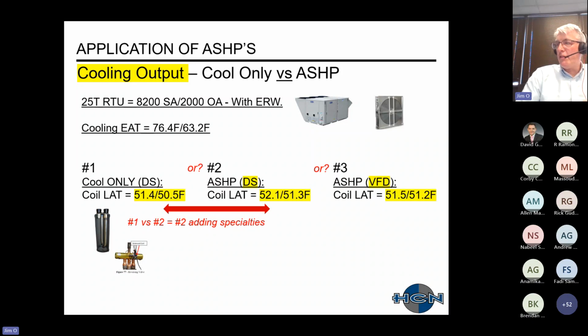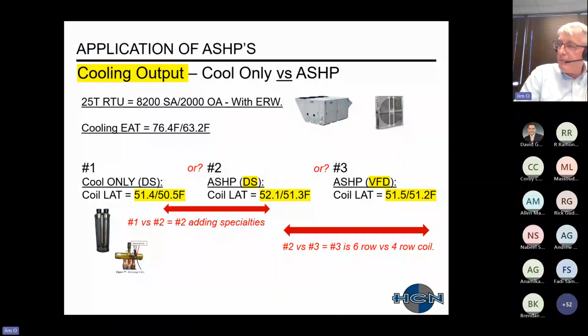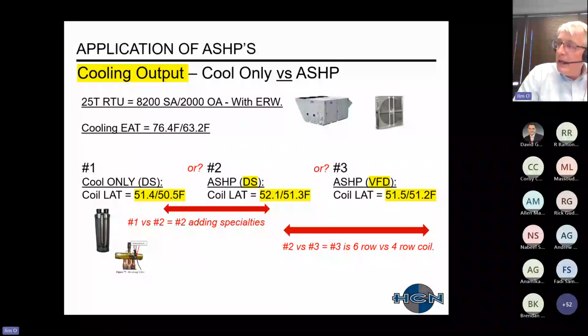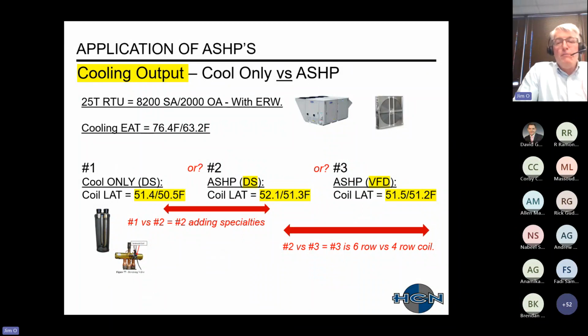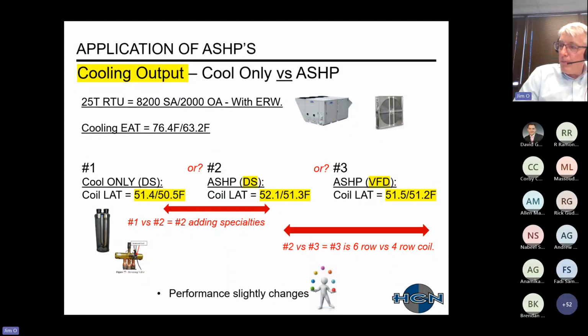And then the other thing to look at is, in the air source heat pump, maybe you have a comparison or available digital scroll versus VFD compressor. There's a little bit better performance on the VFD compressor, but in my example here, what ended up happening was my VFD compressor had a 6-row cooling coil available versus a 4-row. So obviously more metal and more heat transfer is available with the 6-row coil, so you would eke out a little bit more performance. So just realize that your performance might change. I really consider this to be minute and slight. It's not going to disqualify or eliminate a selection of an air source heat pump because my leaving air temperature in cooling rose half a degree, et cetera.